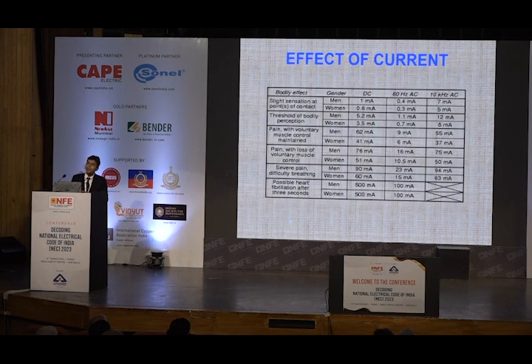This is the effect of current, and if you want to read more, you can see IEC 60479, part 1, part 2, part 3, part 4. This summary I have taken. That depends on whether your body is wet or dry, whether the frequency is 60 hertz, 50 hertz, or high frequency. It also depends on duration.